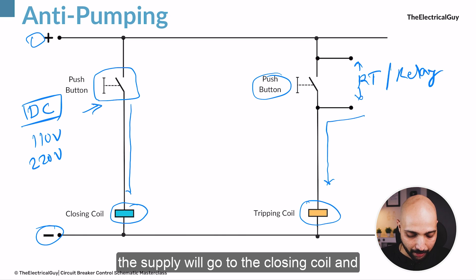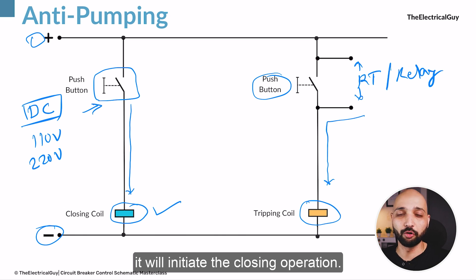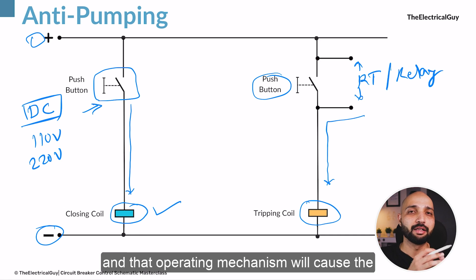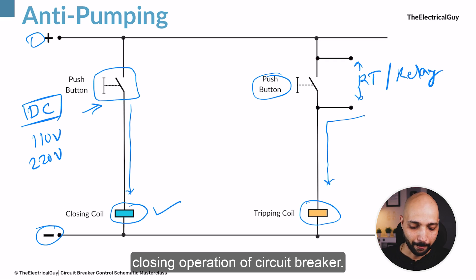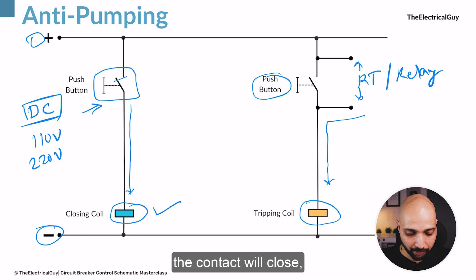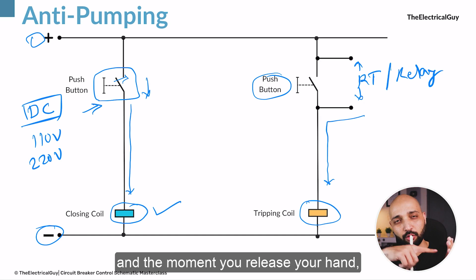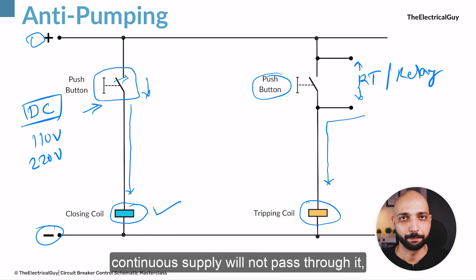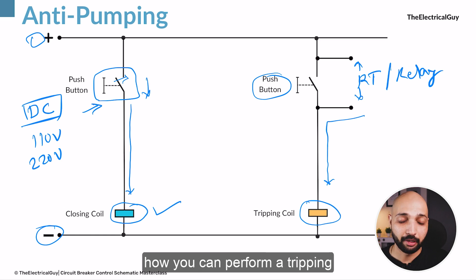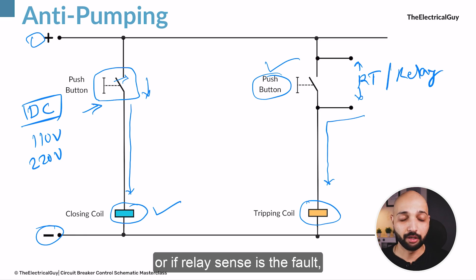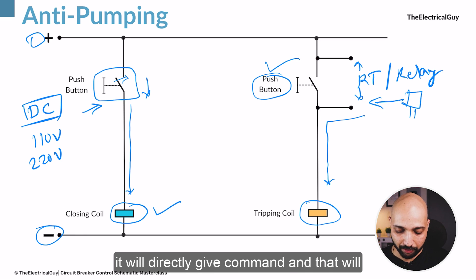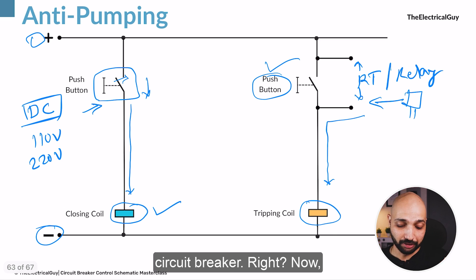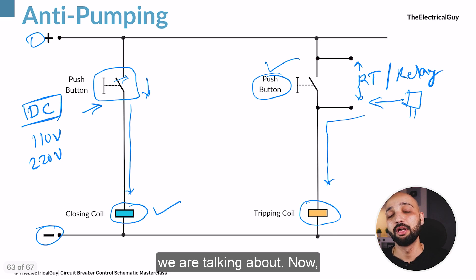When you press the push button, supply goes to the closing coil, which initiates the closing operation — the piston moves, triggering the operating mechanism and causing the circuit breaker to close. When you press the push button the contact closes, supply passes through it, and when you release your hand the contact returns to its original position, breaking the supply so continuous supply will not pass. Similarly, a tripping operation can be performed by pressing the trip push button, or if the relay senses a fault it directly gives the command to the tripping coil.